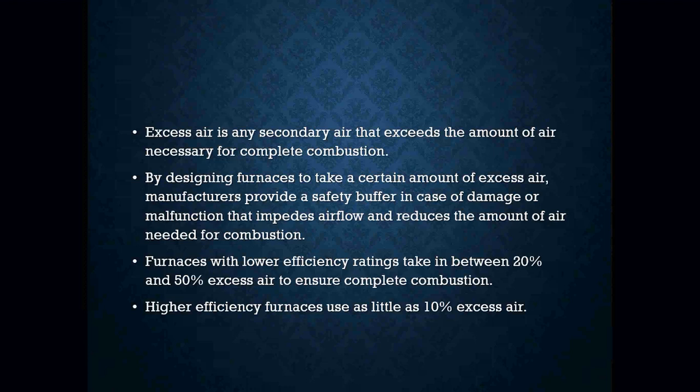Excess air is any secondary air that exceeds the amount of air necessary for complete combustion. So in many ways, you could think of excess air as air that's left over. By designing furnaces to take a certain amount of excess air, manufacturers provide a safety buffer in case of damage or malfunction that impedes airflow and reduces the amount of air needed for combustion. Furnaces with lower efficiency ratings take anywhere between 20 and 50% excess air to ensure complete combustion. Your higher efficiency furnaces use as little as 10% excess air.